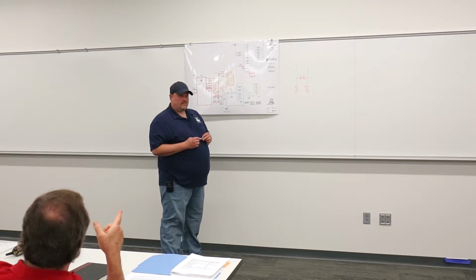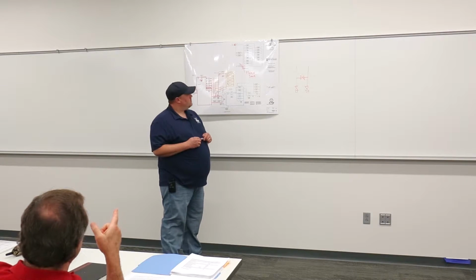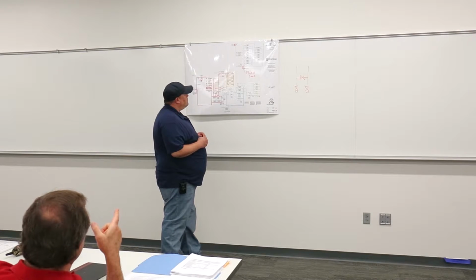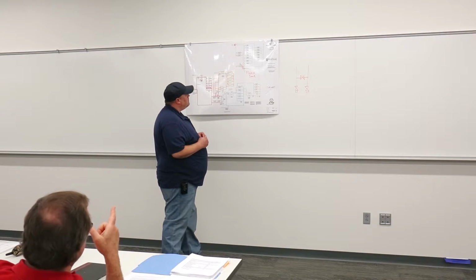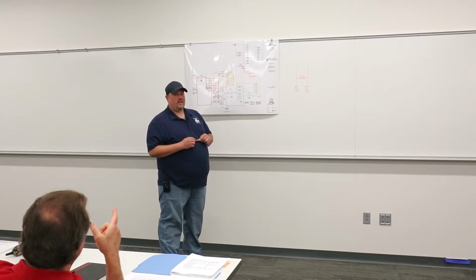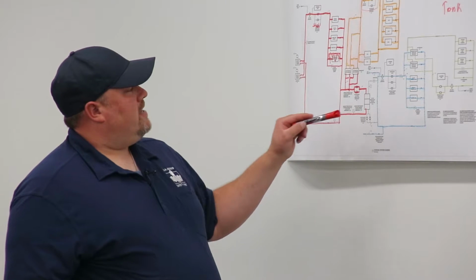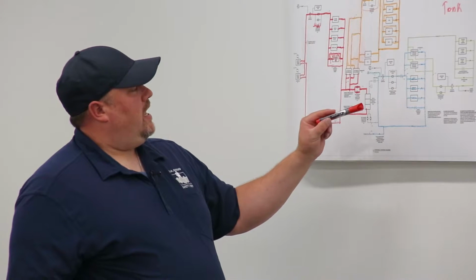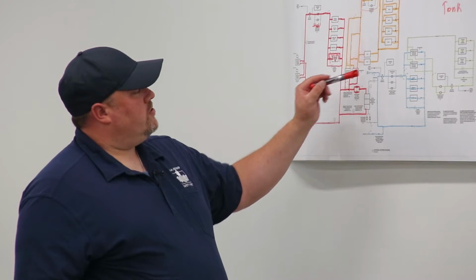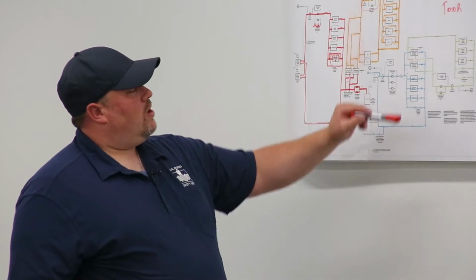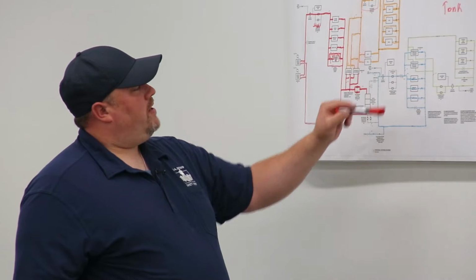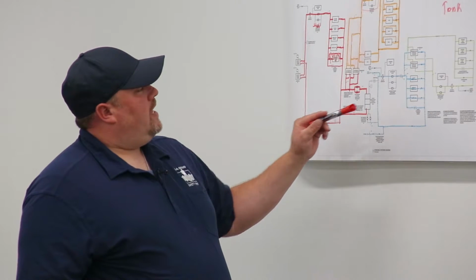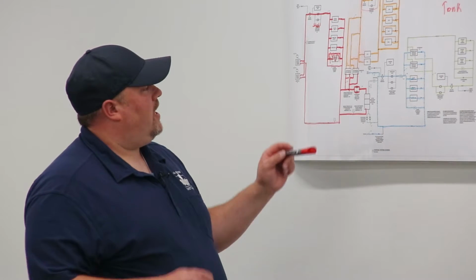The chilled water does not have an expansion tank because, oh no, it does have an expansion tank. Everything's got an expansion tank for the winter operation. Every system has its own expansion tank tied in, because when the chilled water system closes from campus, it becomes a closed loop. At that point, it would need its expansion to where it couldn't possibly expand out to the campus underground utility lines.